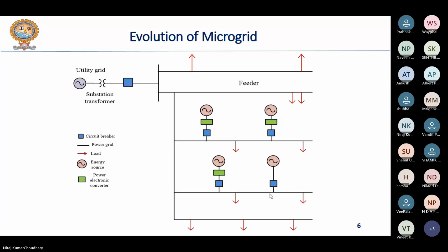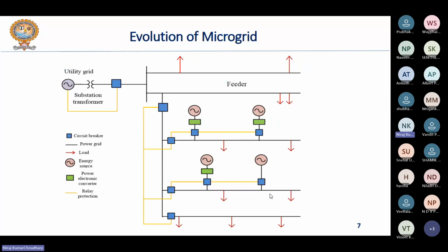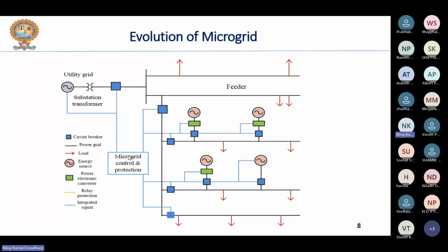Now, the third advancement is the provision of protective devices. Here you can see that the blue square blocks represent a circuit breaker along with the relay combination. Then all the circuit breakers and relays should be coordinated with each other, meaning they should have communication between each other. Suppose a fault takes place on any particular feeder, then the information of that fault should be available to the other relays and circuit breakers in the system also. That's why I have mentioned that there should be coordination among the different relays and circuit breakers present in the system. Now, the final advancement is in terms of the microgrid control and protection unit, which is a centralized facility.